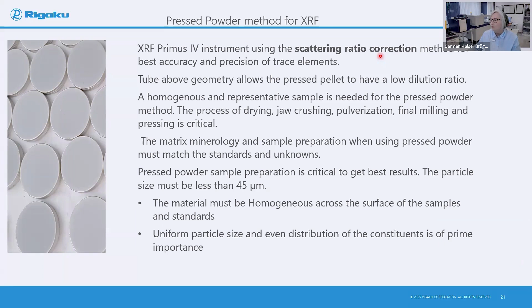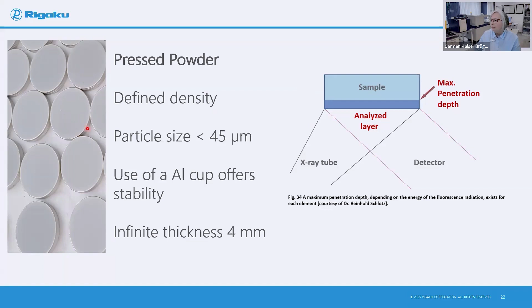So if we look at the pressed powder method, we need to have a defined density. Particle size needs to be less than 45 micron. And in this example, we need to get maximum penetration depth depending on the energy of the fluorescent radiation that we need to measure. So we need to have at least an infinite thickness of 4 millimeters to be able to get the correct penetration depth.